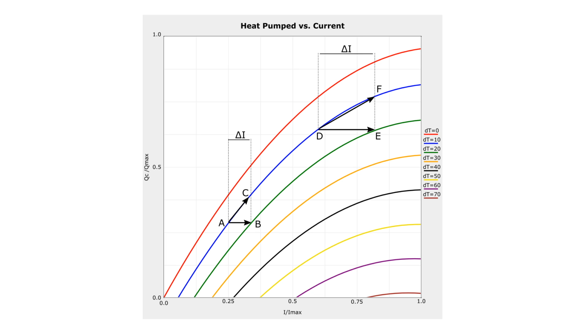If the working point is around 60% of Imax, we need more current than in the previous example to compensate a rise of delta T, point D to E, when the heat pump capacity should stay unaffected. The heat pump capacity can still be increased without losing temperature difference, if we move from D to F.